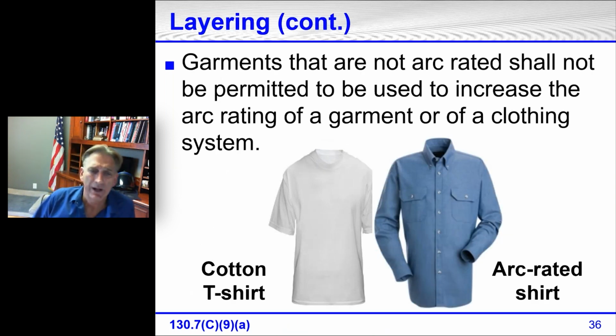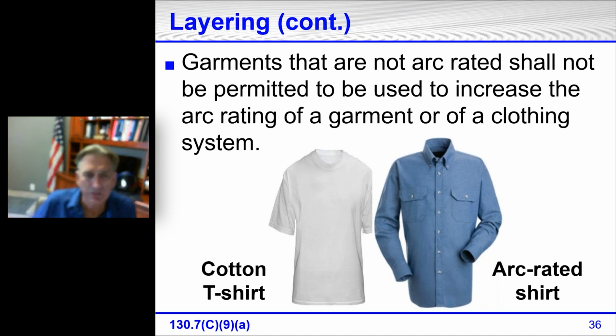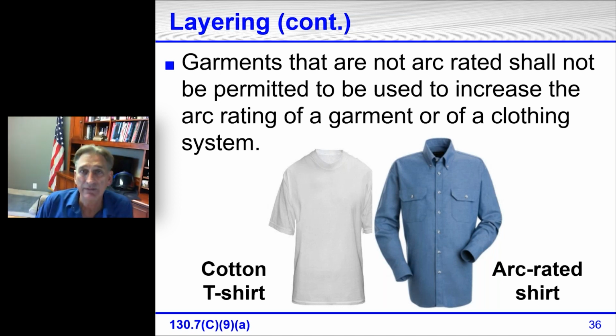All right, so sometimes I'll ask students in class, I've got an arc-rated shirt. The shirt on the right is 8.7 calories per square centimeter. If I'm going to be in front of equipment that has 8.8, would it be okay if I just put on a t-shirt underneath that shirt that's only 8.7? And the answer is no. Garments that are not arc rated shall not be permitted to be used to increase the arc rating of a garment or of a clothing system.